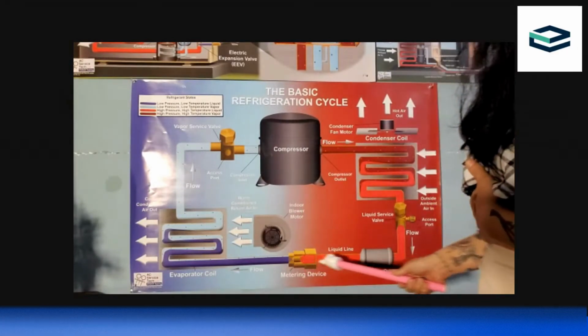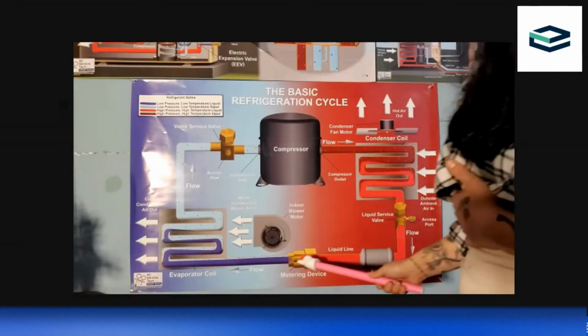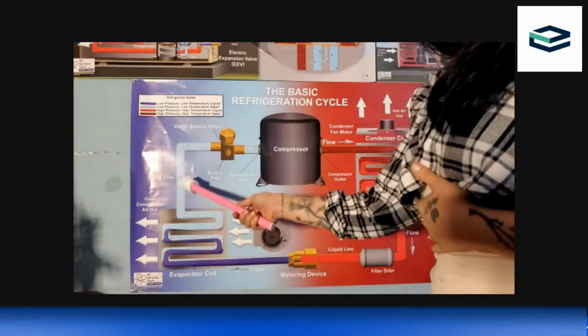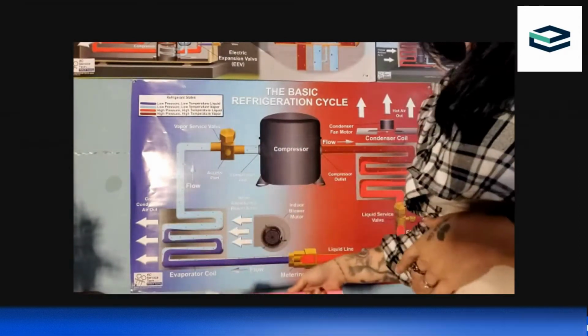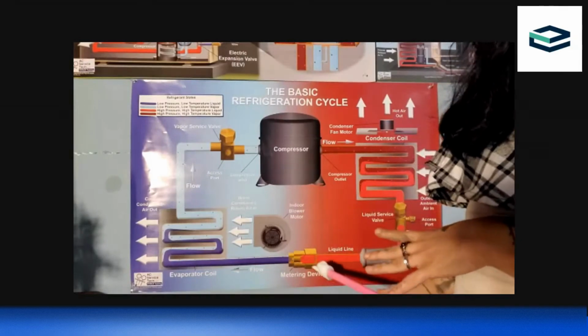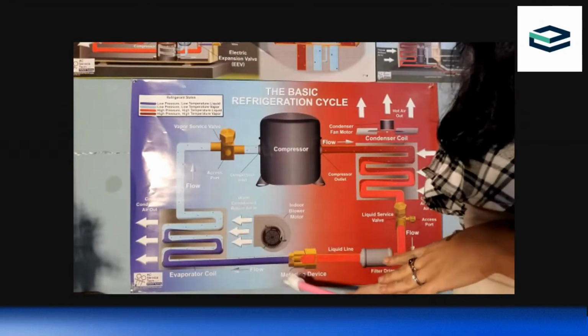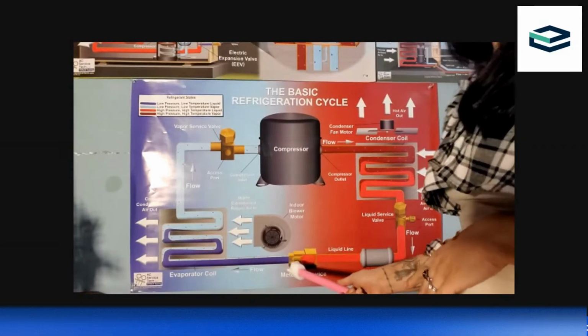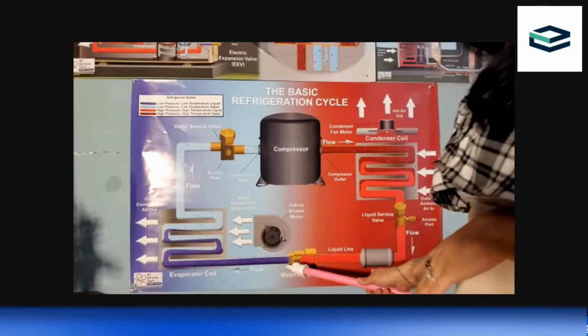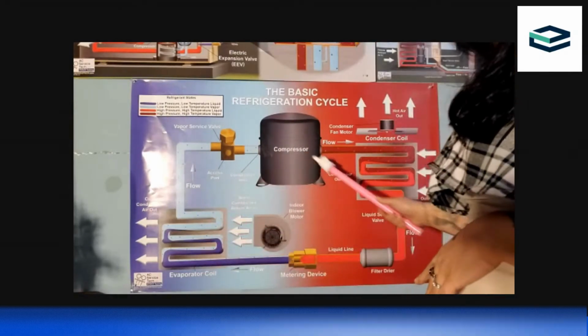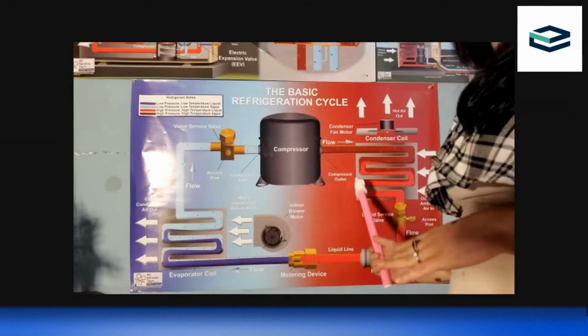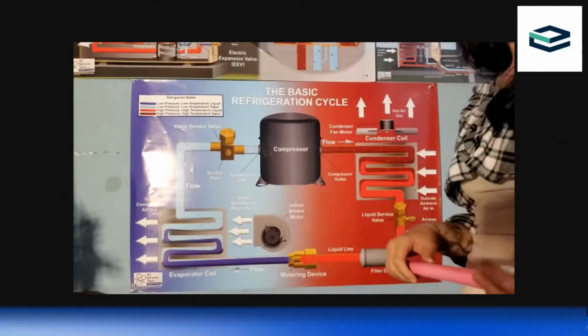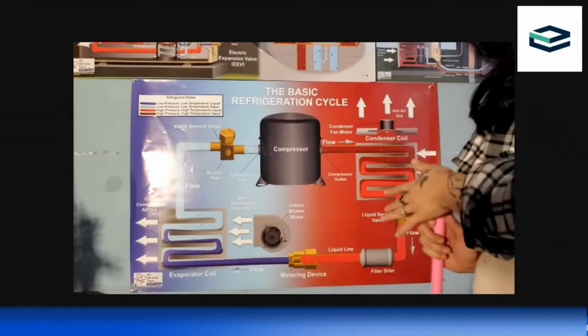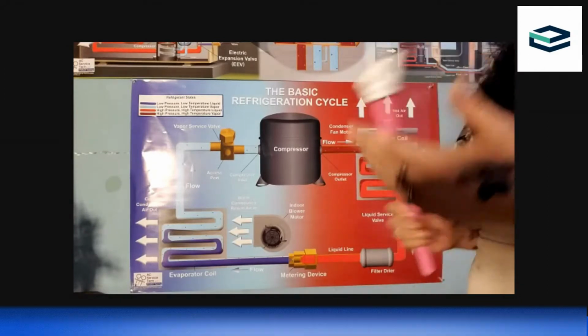So you could end up with all of your liquid on this side and then very little vapor on this side, or very little liquid, depending on where your restriction is. So when that happens, we have got to study this, figure out what we can do to change it. If the whole part needs to be replaced, replace it. And then that way, once it's new and it's replaced again, we're able to start that system back up again. Now, that's not the only reason that your saturation temperatures will be off. If you overcharge or undercharge, they will also be off, because what it's telling you is at what temperature is it mostly liquid, at what temperature is it mostly vapor. If that is not correct, not where you want it, then there is something wrong within the system.